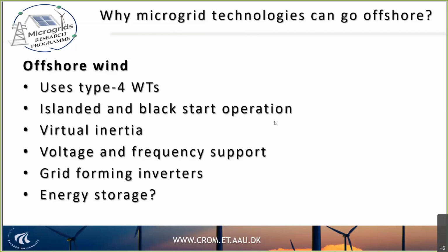Sometimes the offshore wind farm needs repair—the cable can be broken or cut, or there could be blackouts outside. Because of that, you need to be able to operate in island conditions, otherwise restarting the whole wind power plant takes a long time. Right now, unfortunately, diesel generators are required to energize the plant, which goes against the philosophy of promoting renewables. That's why we think black start operation needs to be there.